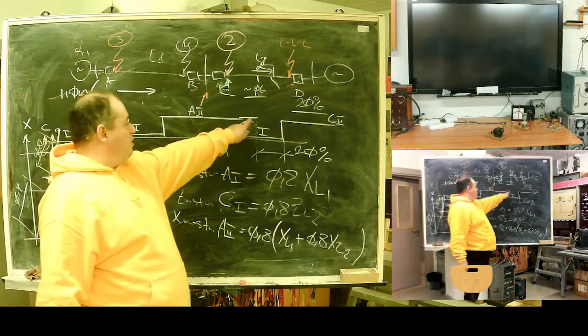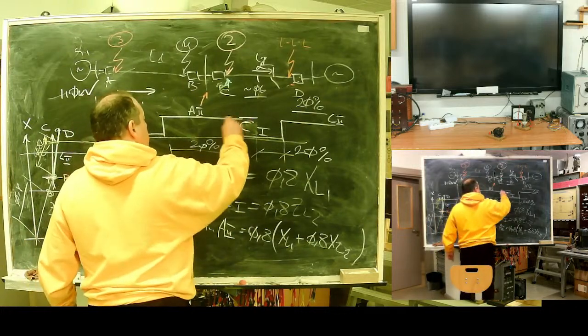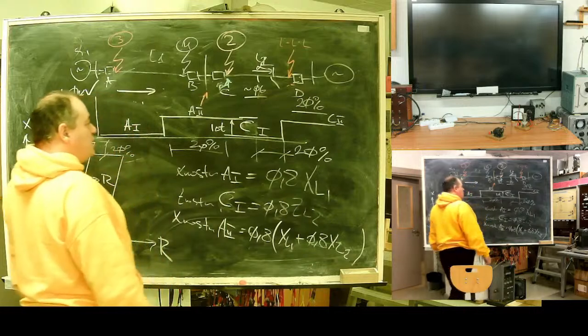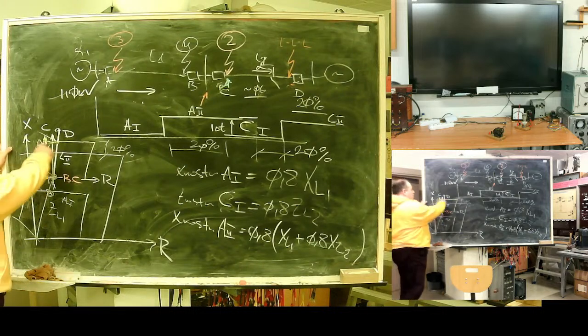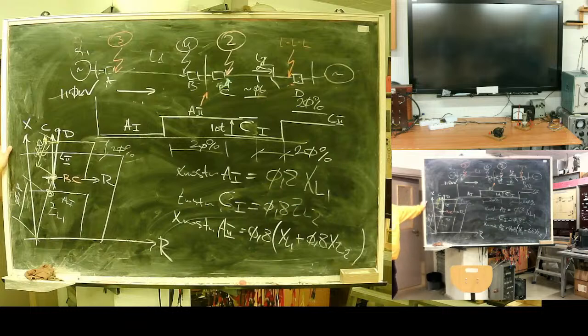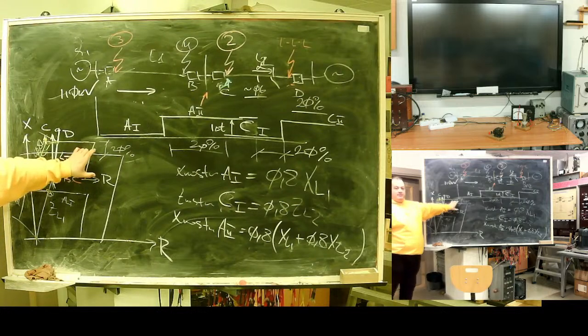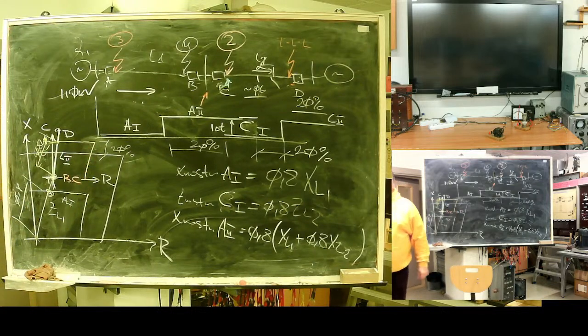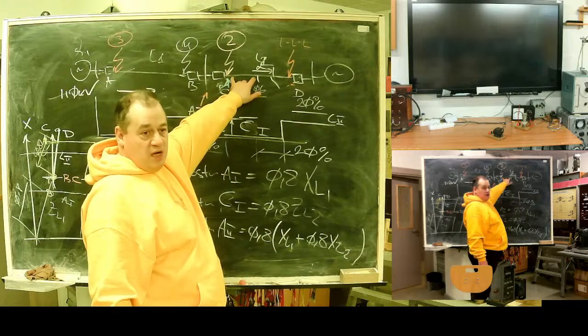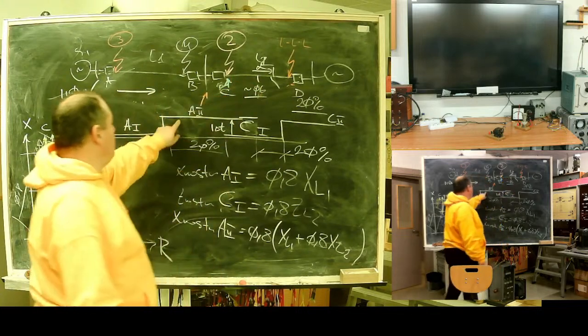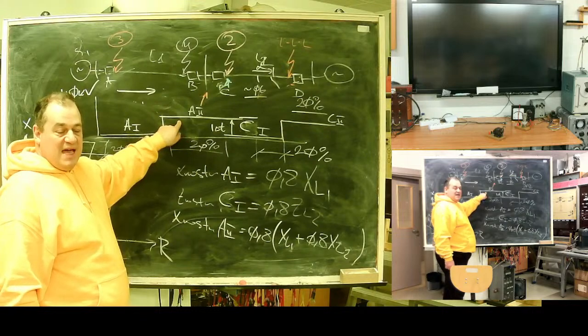See where they overlap? Here should be 1 delta t times time separation. But do you see what this violet is? An operation area of the A second zone. Yellow is an operational area of C1, sorry. See they overlap. Redundancy.